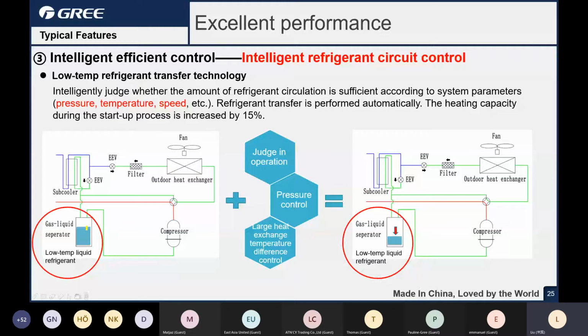And for the GMV6, we can judge if there is too much liquid refrigerant inside the gas liquid separator, according to the system parameters such as the pressure. Here the low pressure and the high pressure, temperature and the speed. There is the inlet and the suction, and we judge according to the difference here and also the pressure difference.